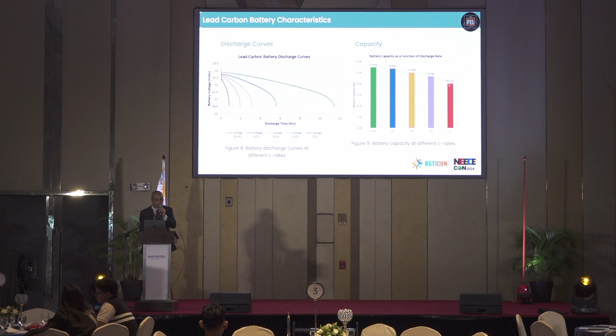And if you compare this to lead acid, at 1 C discharge rate, meaning if it's 24 ampere hours, you discharge it at 24 amps. At that rate, the capacity you will get is already going to be about 50% of the rated capacity for standard lead-acid batteries. If you look at the numbers here, the 24 ampere hour battery actually still gave us 20 ampere hours. So 20 ampere hours is, what percent is that? Around a little over 80%. So it's a lot better than lead acid.